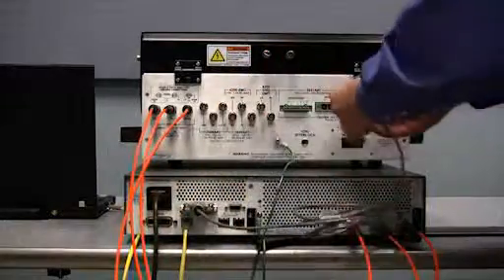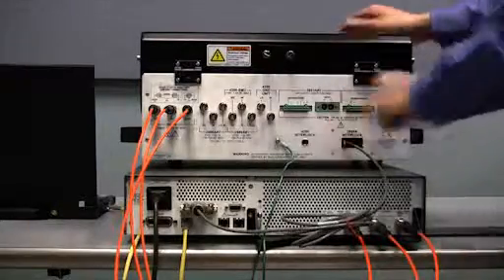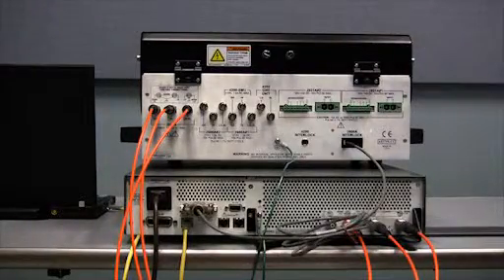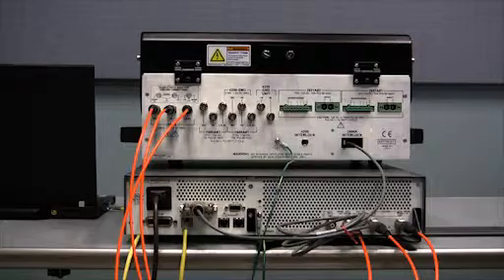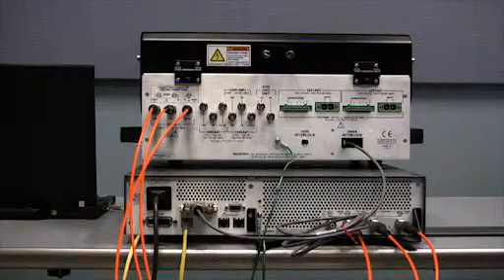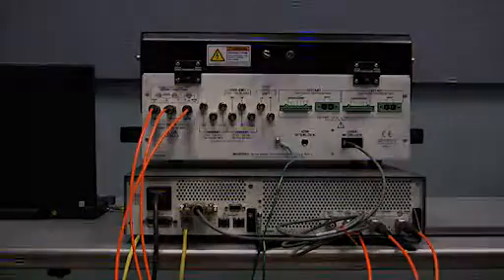The model 8010 is equipped with redundant dual interlock safety switches ensuring that when the lid of the test fixture is opened the high voltage output is disabled maximizing system safety.